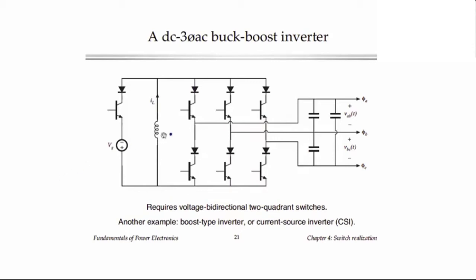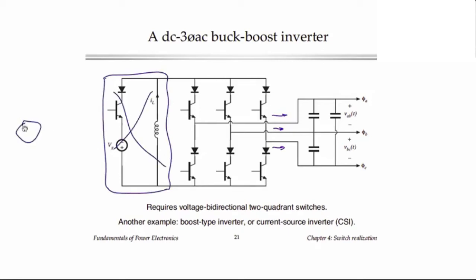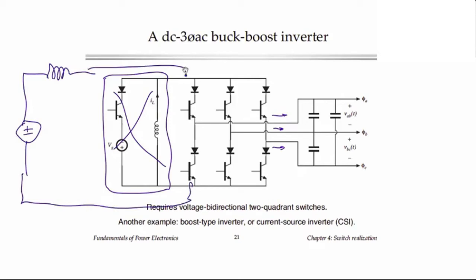Basically we can build a DC to three-phase AC inverter that synthesizes output-side current waveforms that are sinusoidal. A well-known converter similar to this is called the current source inverter, which can be viewed as derived from the boost converter. Inside that circuit we replace part of it with a DC source and an inductor. That inductor carries a current with small ripple, which is switched to the different three-phase outputs to synthesize sinusoidal output current waveforms. It's called the current source inverter and it requires voltage bidirectional switches as well.